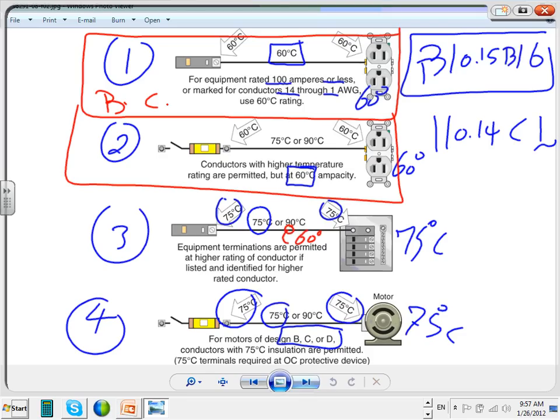You go higher than number 1, you get into the feeders. Most likely when you get higher than number 1, it's in this area. We're talking about feeders. The only exception is motors. Motors are the only exception. This is branch circuit, but with the exception for motors, though. B, C, and D design. Remember, Nick, we talked about the design a few minutes ago. Design C. A is not here though. B, C, and D. The most common design we talk about all the time is what? Design B. So all your air handling units, all your chillers, everything is going to be design B.